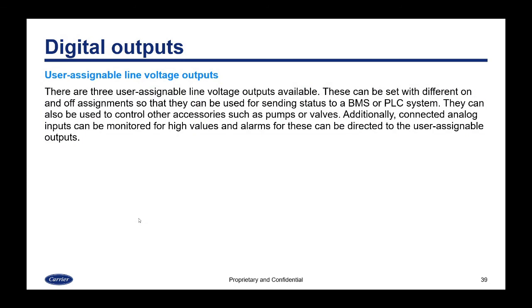There are 3 user assignable line voltage outputs available, and these can be set with different on and off assignments, so they can be used for sending status to a BMS or a PLC system. They can also be used to control other accessories such as pumps or valves. Additionally, connected analog inputs can be monitored for high values, and alarms can then be directed to the user assignable outputs. So you can have an analog input monitoring a temperature, and when you reach a high temperature threshold, you can assign one of these line voltage outputs to turn on when you reach that threshold.